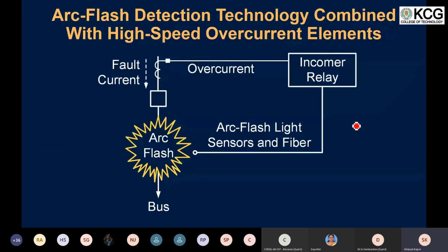And one of the best and the most economical ways, I can say, and a novel approach to mitigate this kind of fault is using arc flash protection. The reason being that this kind of arc flash protection doesn't require the relay to be connected to any of the switches. There is no communication requirement between any relays. So it eliminates the threat of cyber attacks. And also the time associated with the relay operation is much faster when we implement this kind of arc flash sensor based arc flash mitigation. And here we are still going to maintain the time coordination between the incomer and the outgoing, and we are not going to lose any coordination, or there is no threat of losing the entire switchboard if the fault were to occur on the outgoing system.